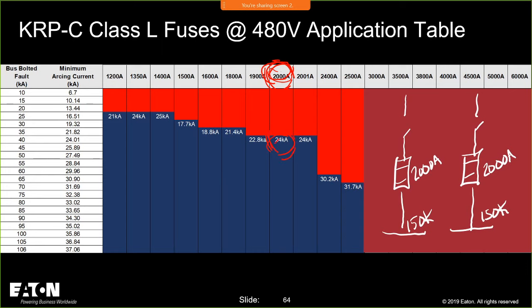I could show this to the inspector and say, look, a 2,000 amp fuse has a clearing time of 0.07 seconds and faster when the bolted fault current is at least 24,000 amps. You have 150,000 amps in your project. So whatever the arcing current is at 150,000 amps, it's going to be greater than what the arcing current is at 24,000 amps. So that will give the inspector something they can understand to say, now I know you're going to be clearing faster than 0.07 seconds, because for a 2,000 amp fuse, anything greater than 24,000 amps gets you into that region. Now I believe that is something that can be logically understood, and it is technically valid.